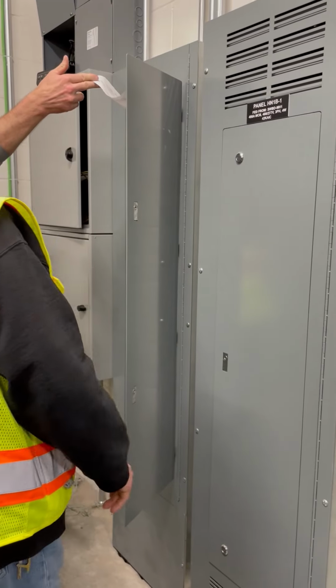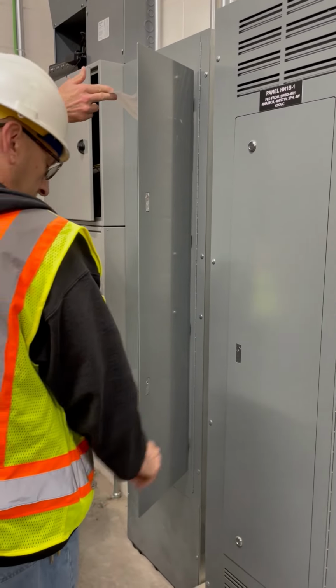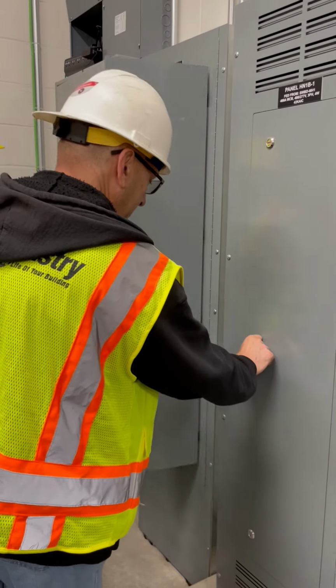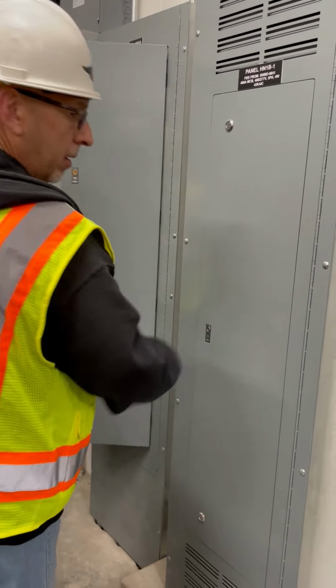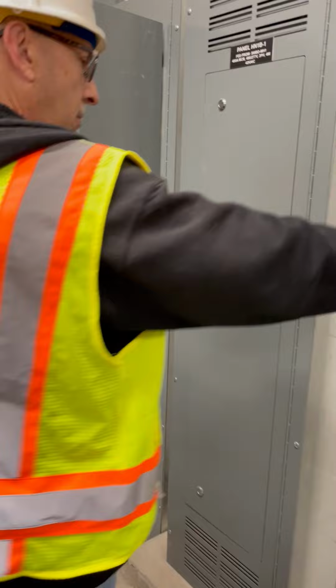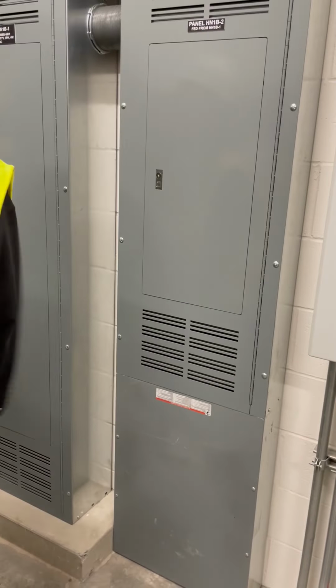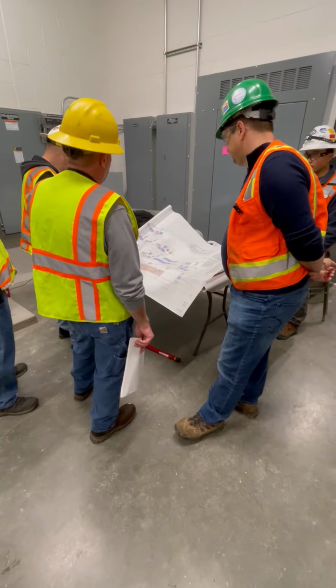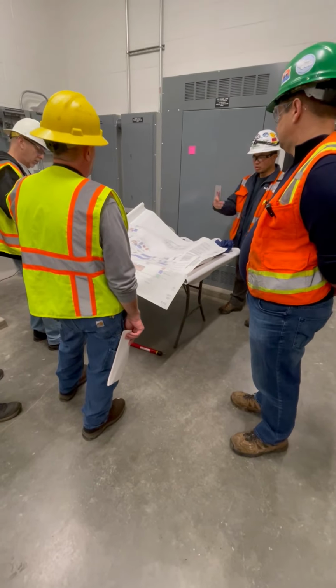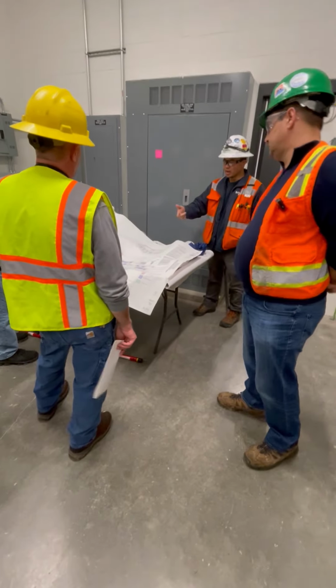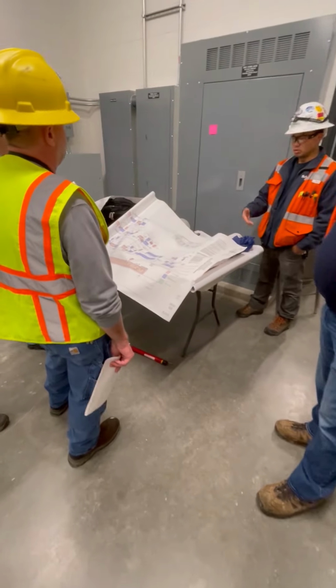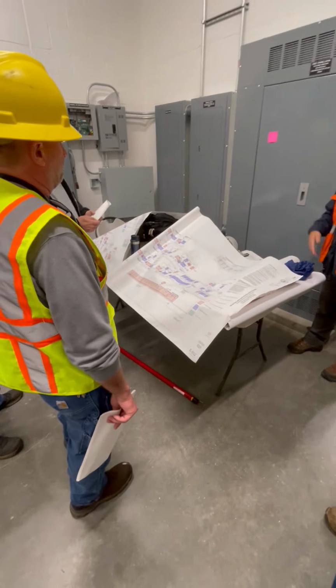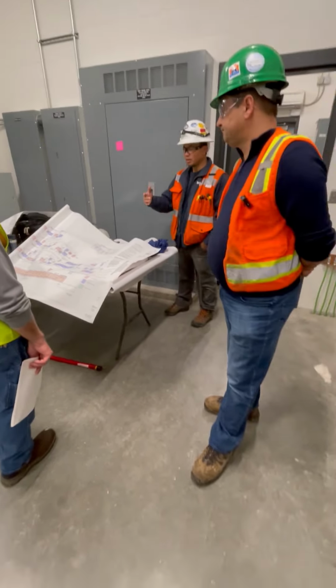They need to be not on the inside; they normally get placed on the outside, before you open the cover. Okay, this one was on the inside, which is fine. But typically you put it on the front end. And if an electrical contractor comes to do any work, you want to make sure this gets updated. If you're adding a panel, add it to the drawing, because over time it gets messy.